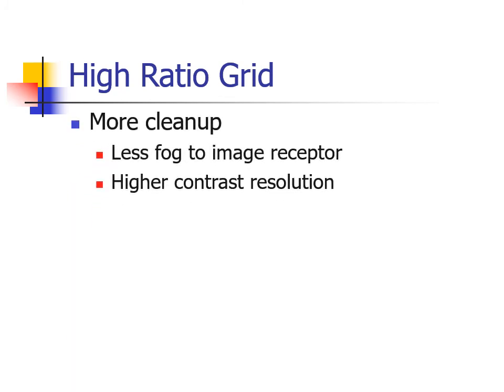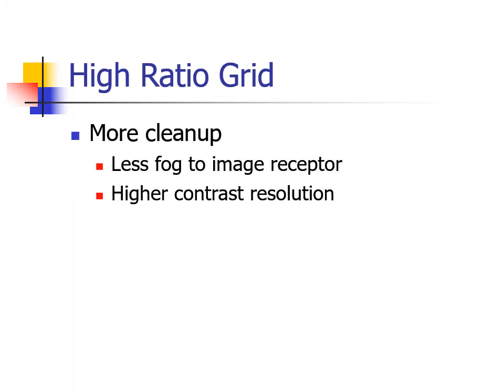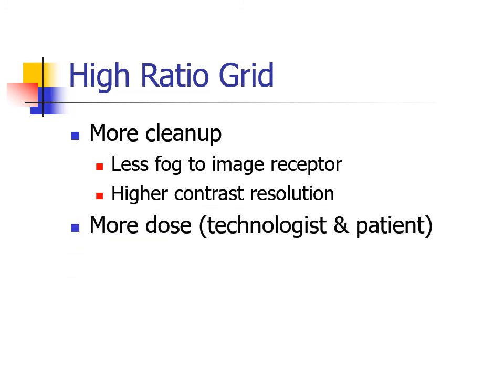So, the advantages of high-ratio grids are less scatter reaching the image receptor and higher contrast resolution. The higher the ratio, the larger the dose to the patient and possibly the radiographer. High-ratio grids are more subject to grid cutoff and mostly used in fixed applications where the orientation of the grid can be rigidly controlled.